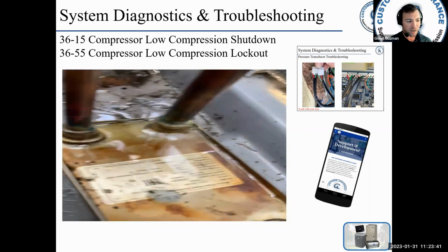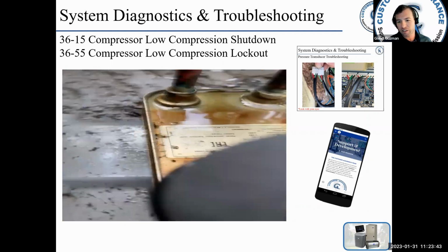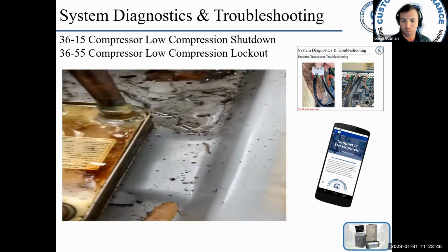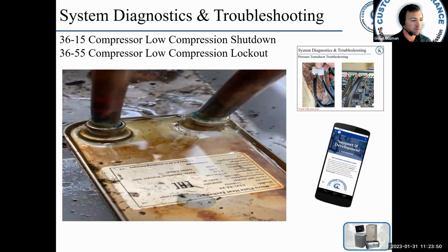Low compression shutdown and the lockout, that's 3615 and 3655. Again, most of the time that occurs is due to a leak. I'll show the video again. You can see clearly a leak. Any leaking component could cause low compression. Okay.